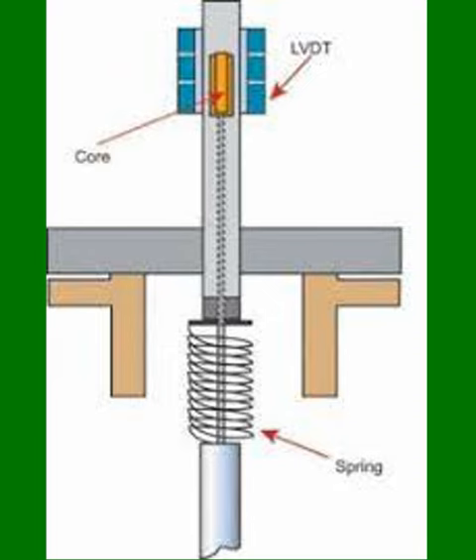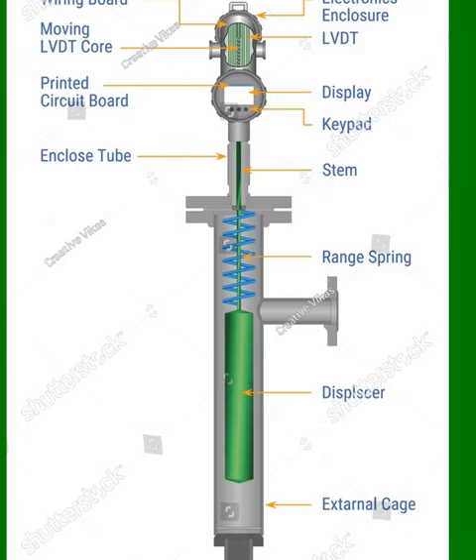But what about the spring? This is where it gets interesting. The spring mechanism opposes the upward force exerted by buoyancy. As the liquid level changes, the buoyant force does too, causing the displacer to move up or down. This movement doesn't go unnoticed — a position transmitter steps in, converting the movement of the displacer into a proportional electrical signal.